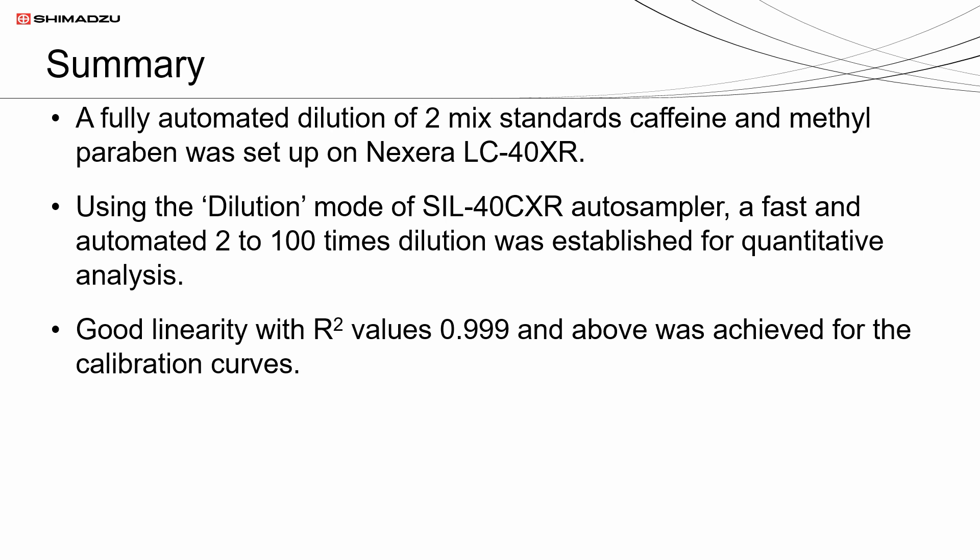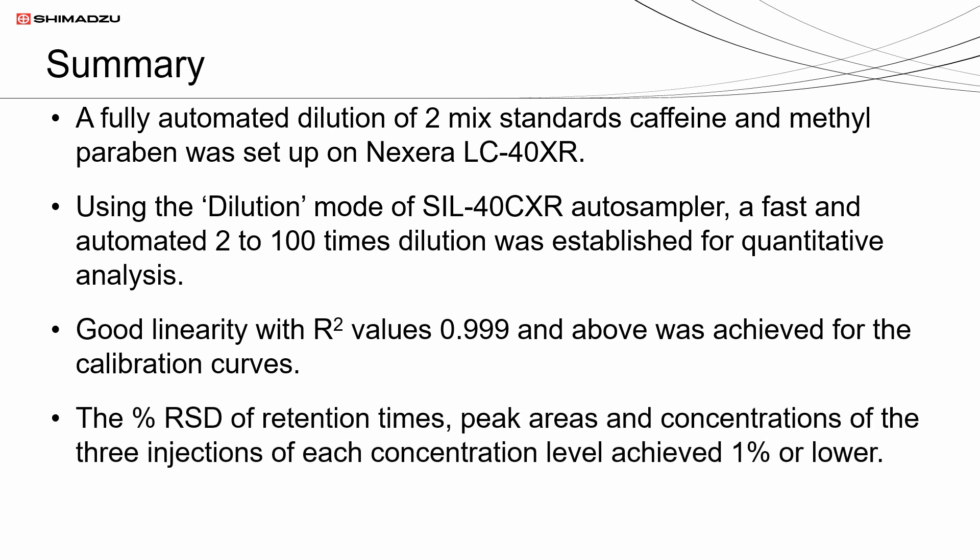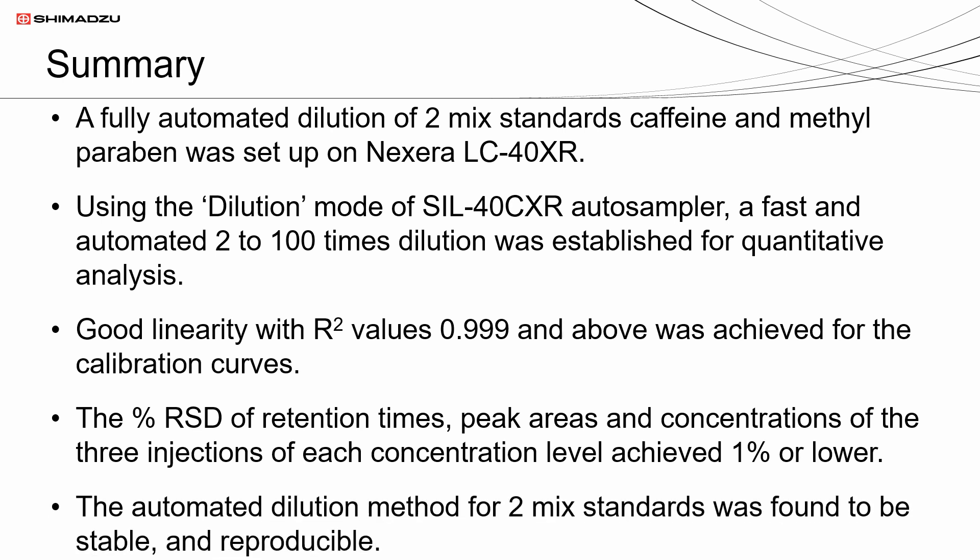Good linearity with R² values of 0.999 and above was achieved for the calibration curves. The percent RSD of retention times, peak areas, and concentrations of the three injections of each concentration level achieved 1% or lower. The automated dilution method for two mixed standards was found to be stable and reproducible.